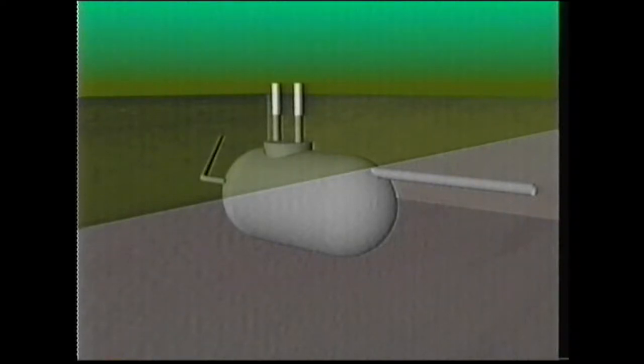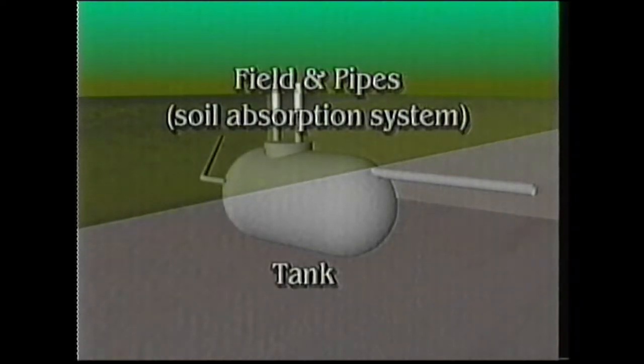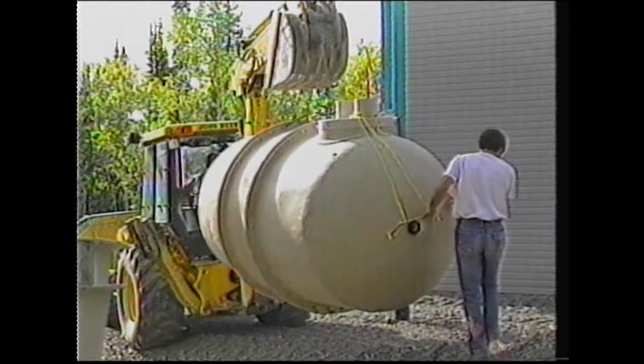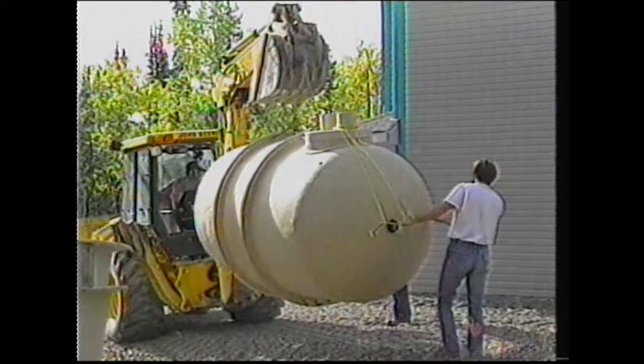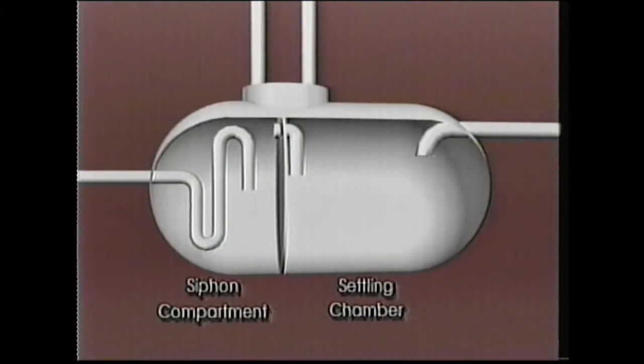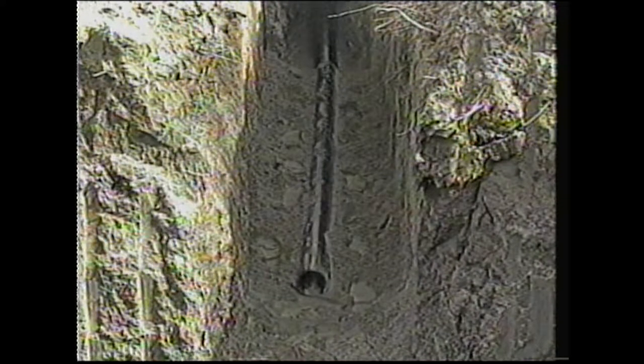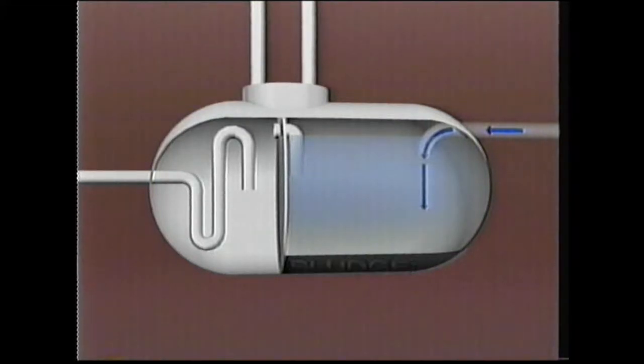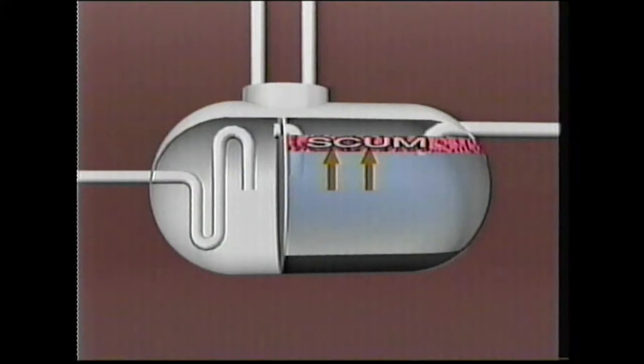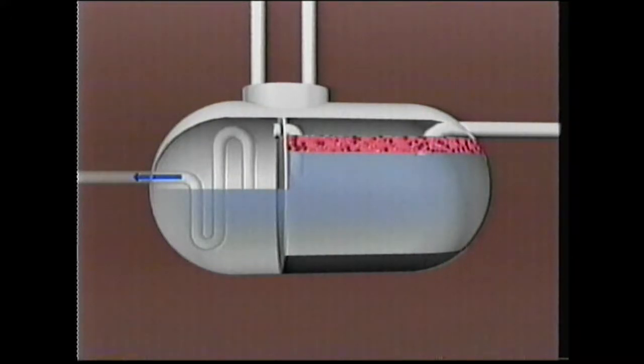What does the typical system look like and how does it work? Conventional systems comprise a septic tank and a soil absorption system. While there may be many different shapes and sizes, all tanks are designed to do the same thing: separate the solids from the liquids and produce a treated effluent suitable for discharge to the soil. A septic tank has one or more settling chambers and may be fitted with a siphon compartment. The sewage travels from the house through a solid pipe to the settling chamber, where the solids settle. Scum floats to the top, and only the relatively clear liquid is allowed to pass into the soil absorption system. In addition to separation of solids, treatment occurs from bacterial breakdown of the organic material.